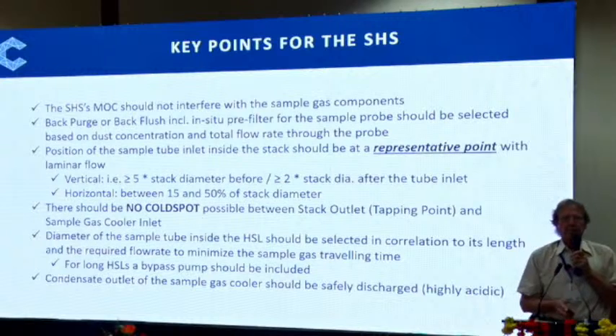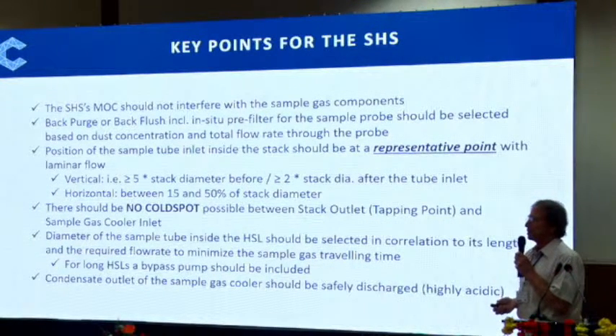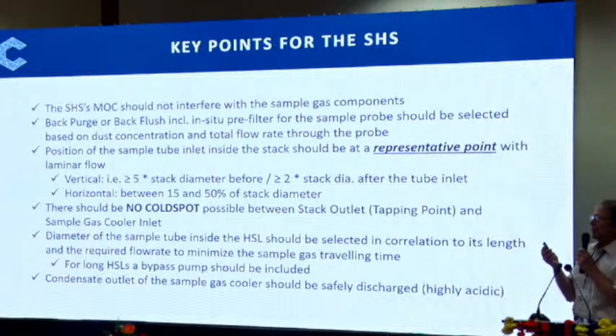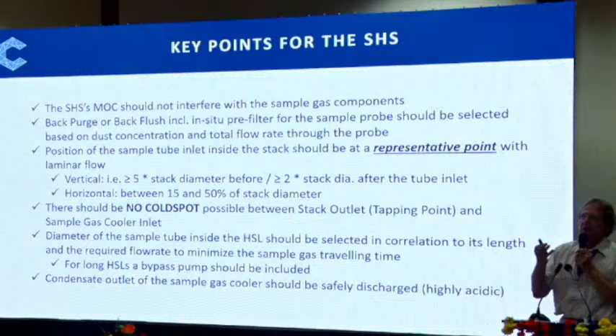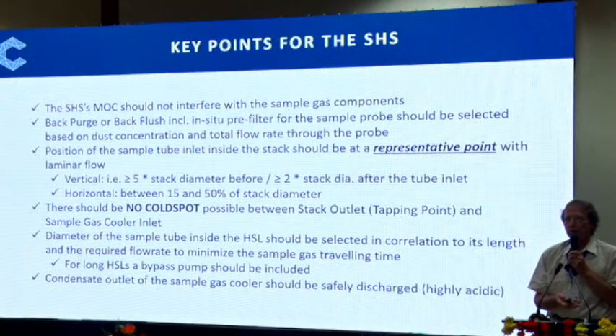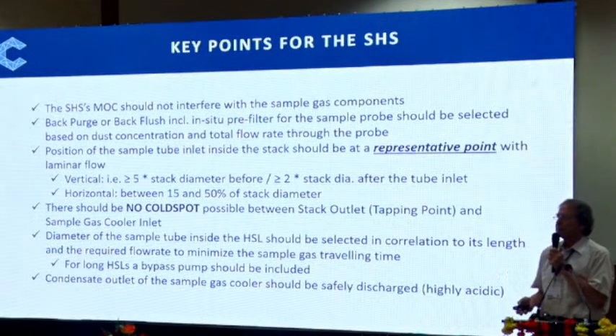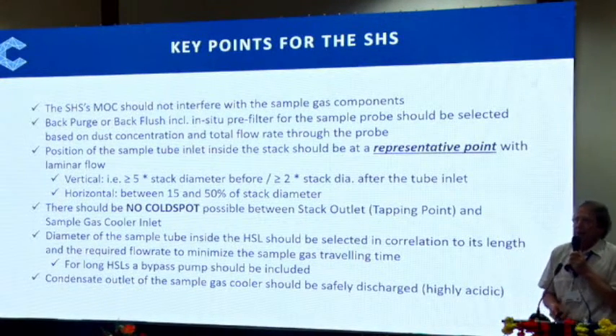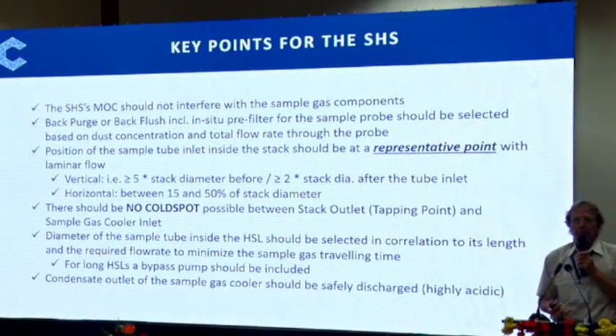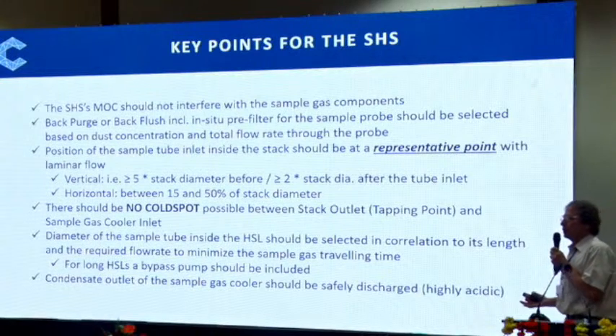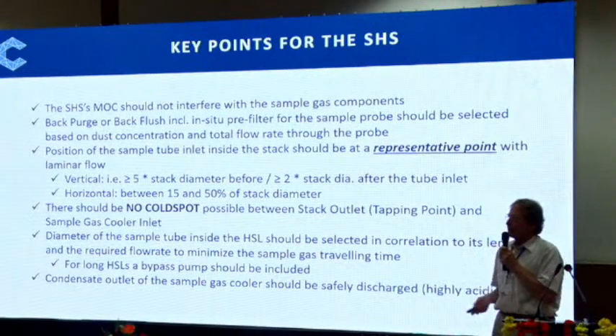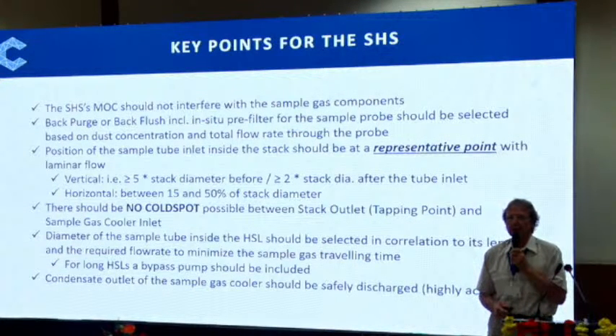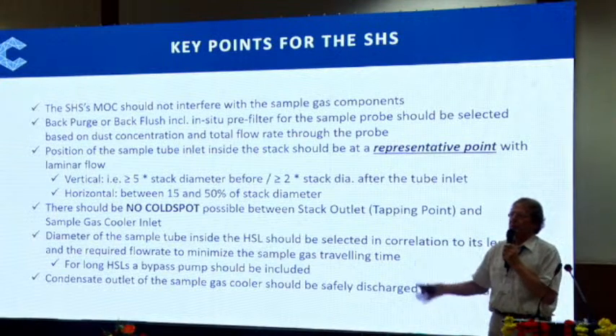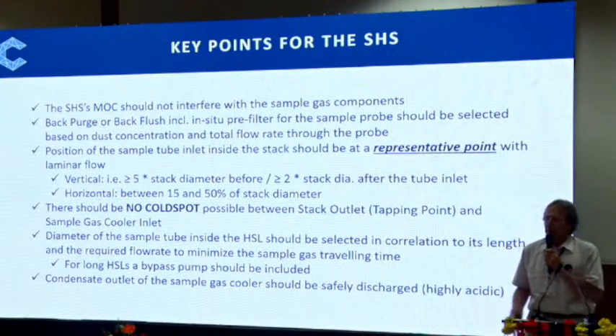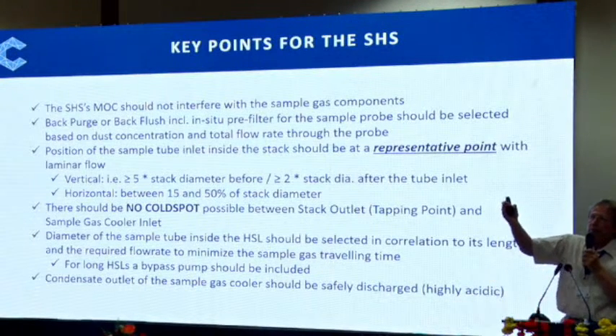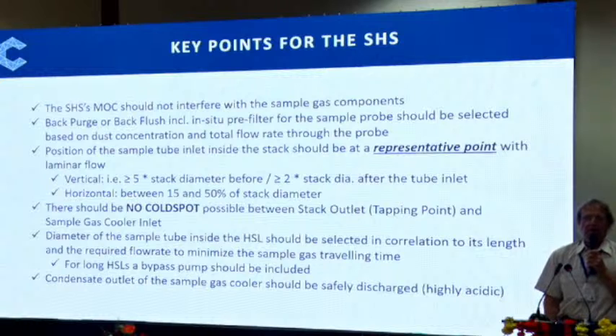Very, very important on sample handling systems: no cold spots. Any cold spot creates condensation. Any condensation creates not only corrosion of my system, it also dilutes or takes out components I want to measure. So any cold spot has to be avoided. And we've seen pictures from what Sanjeev showed yesterday. You could just see the cold spots in these negative examples. So that is a very important part. No cold spot from the outlet of the stack until the inlet of the sample gas cooler.